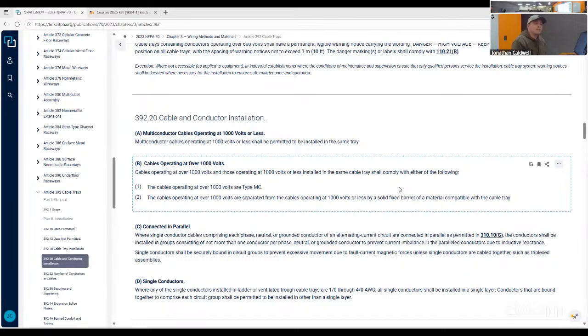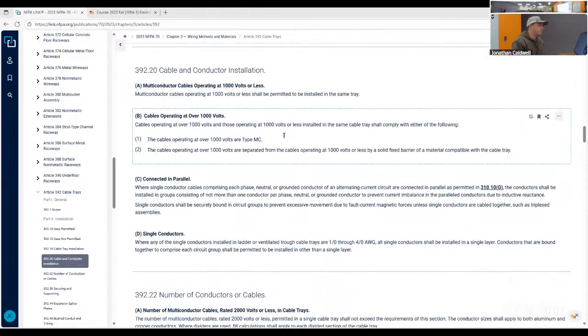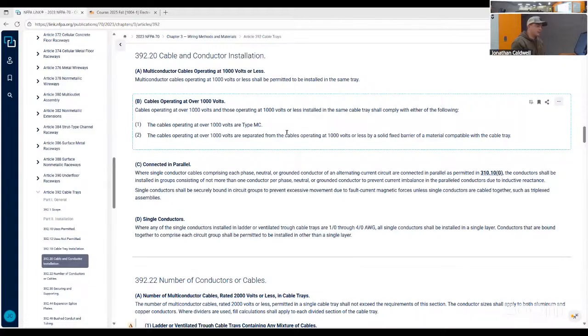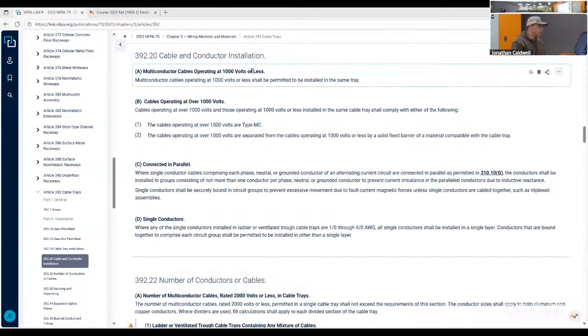Like for instance, there's no amperage on this, so testing it should probably be fine, but when we were doing some troubleshooting on some start-stop circuits, for a circuit that was supposed to be dead, and it was, I was seeing 50 volts to 70 volts. And that's just because of how much current and the amount of cables that are going in that tray. That's just an induced voltage, and that's what happens. So if those weren't rated the same insulation, I would probably see 120 volts or whatever the voltage is with that. That makes sense. So it's extremely important to make sure your insulation is matching with each other, if you do this.